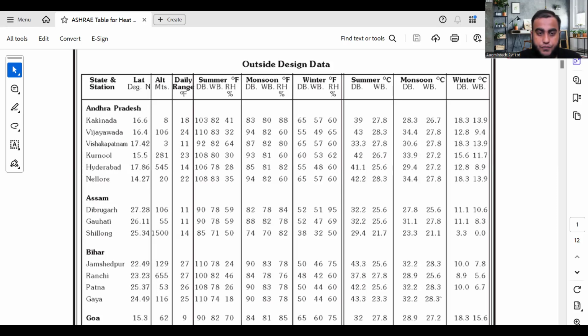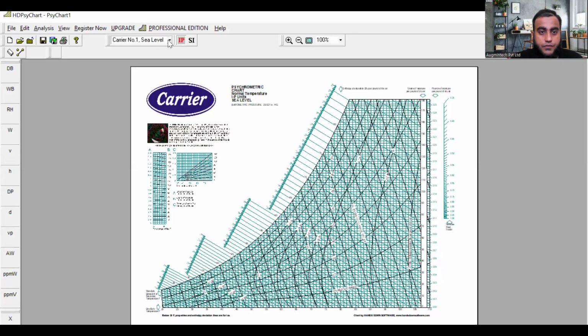So now open your software. First of all, from this software, you have to select the sea level. So our sea level for Hyderabad, how much is it coming? Less than 2,500 feet, right? Sea level is less than that, so you have to select the carrier number first. In case you're designing for any location where the sea level is 2,500 feet or more than that, you have to select the second number. But in our case, I have selected carrier number 1.